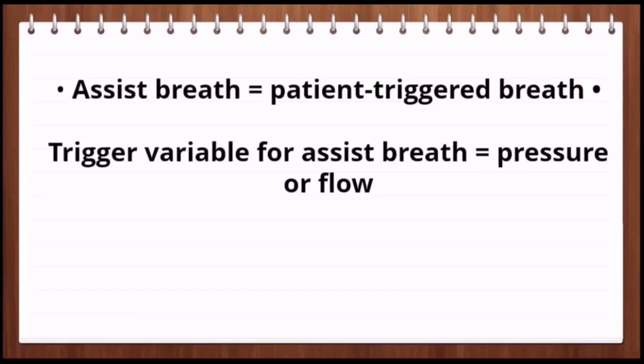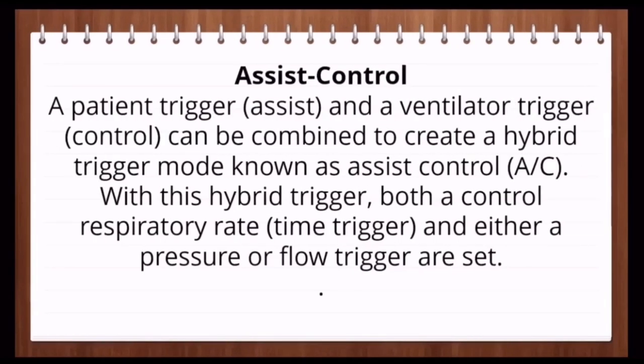Simply put: an assist breath is a patient-triggered breath. The trigger variable for an assist breath is either pressure or flow. Now, assist control combines patient trigger (assist) and ventilator trigger (control) to create a hybrid trigger mode known as assist control. With this hybrid trigger mode, both a controlled respiratory rate (time trigger) and either a pressure or flow trigger are set together.